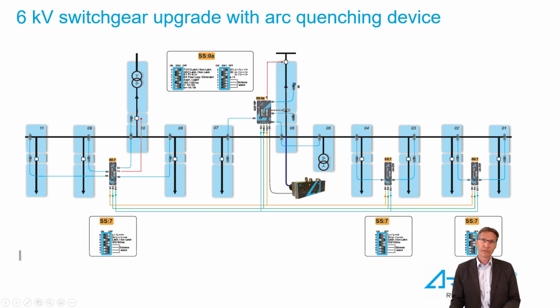In the incoming feeder, we do have a current monitoring relay, since the protection principle is typically applied on 2 criteria, light and current. So dual tripping criteria is typically recommended in critical applications. Here, obviously, a very critical piece of switchgear, since any outage here would put the plant down.